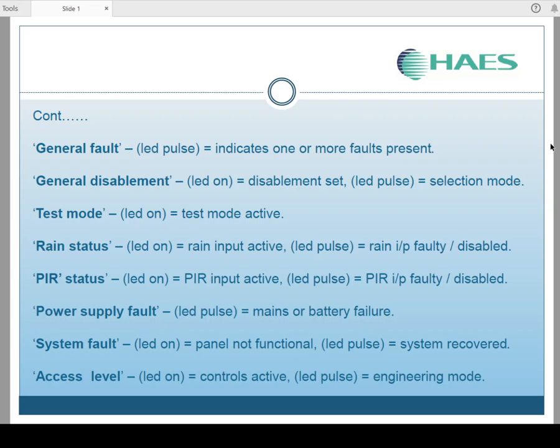Power supply LED, or sorry, the power supply fault LED. If it's pulsing, it means you've got a mains or a battery failure. The system fault LED, LED on means the panel is non-functional, or is literally useless really. If the system fault LED is pulsing, it means it's recovered from a serious system fault. It's just to let you know.